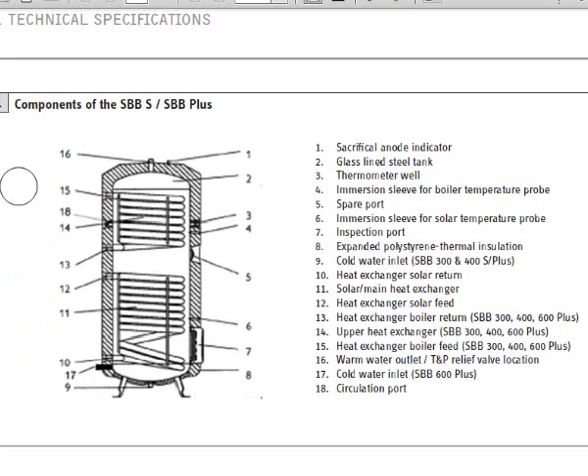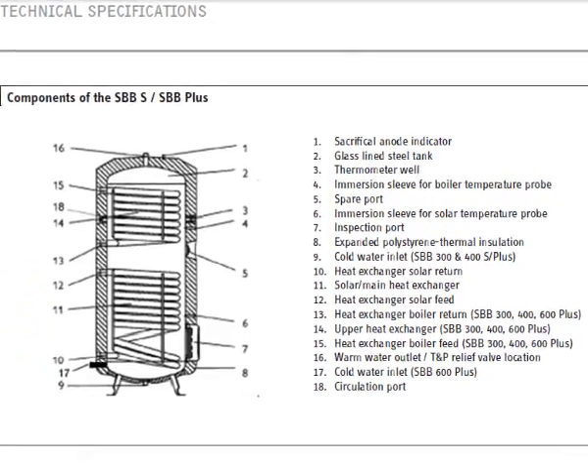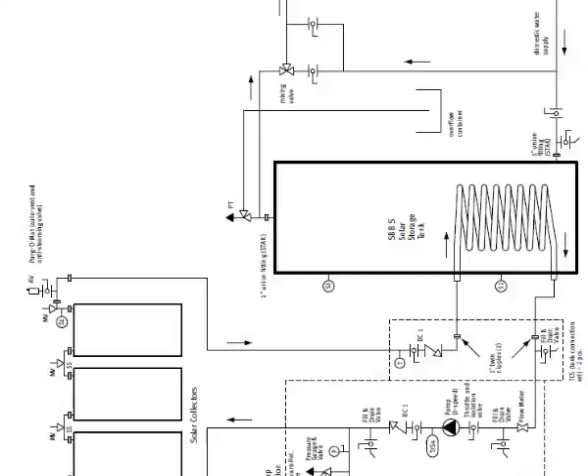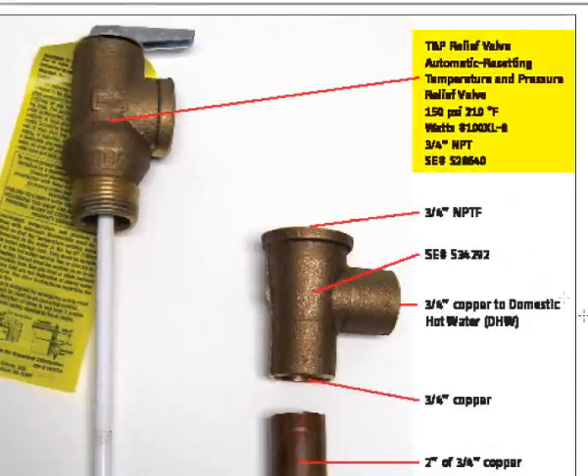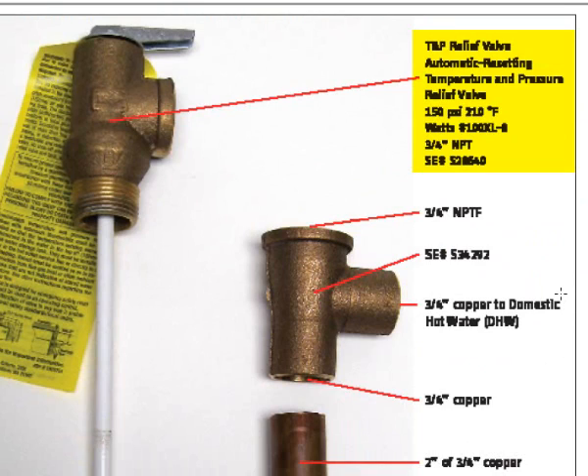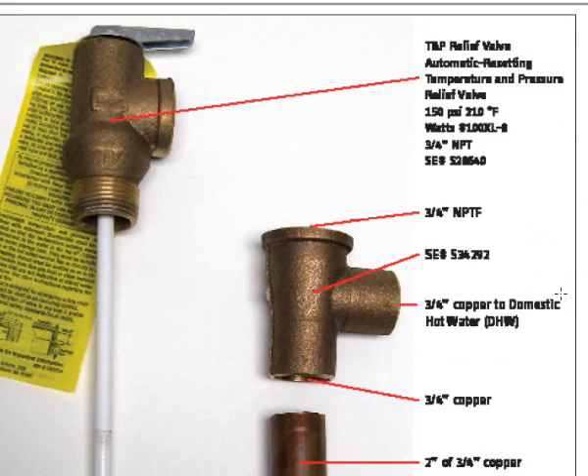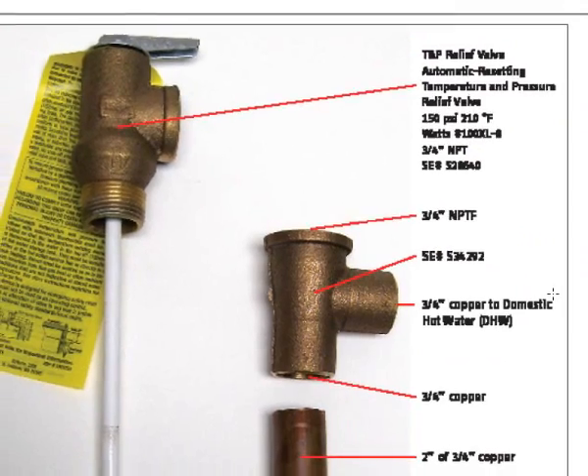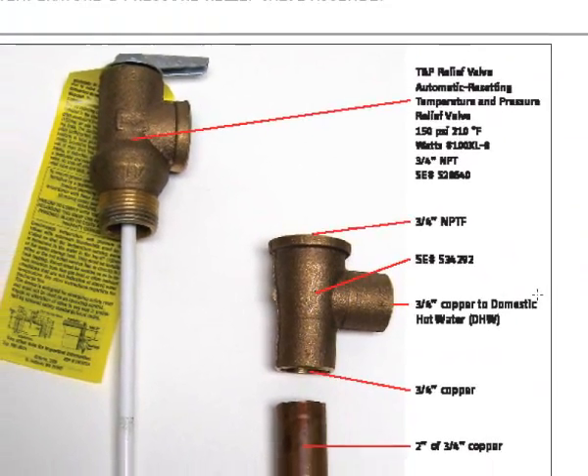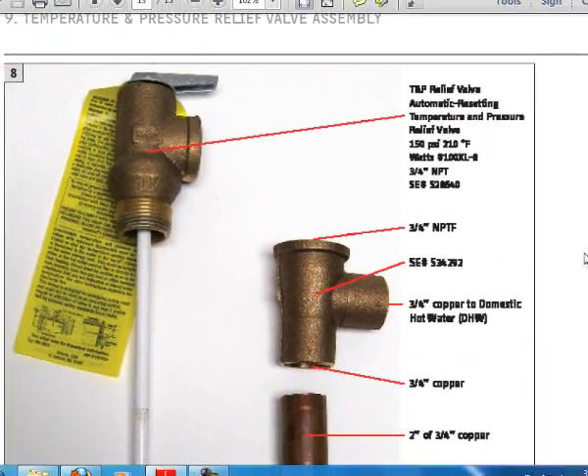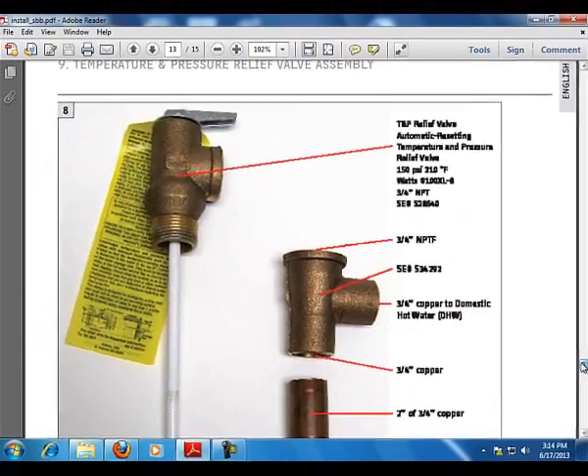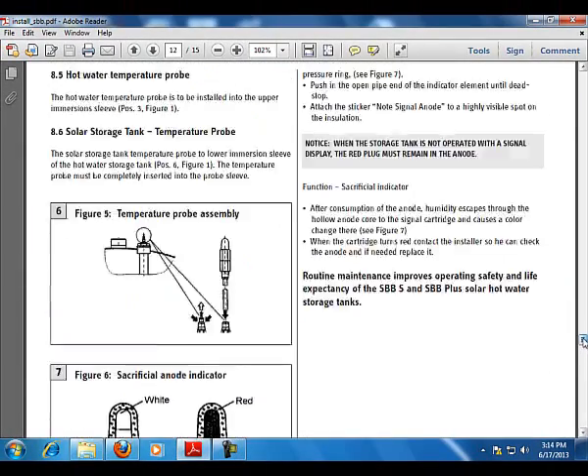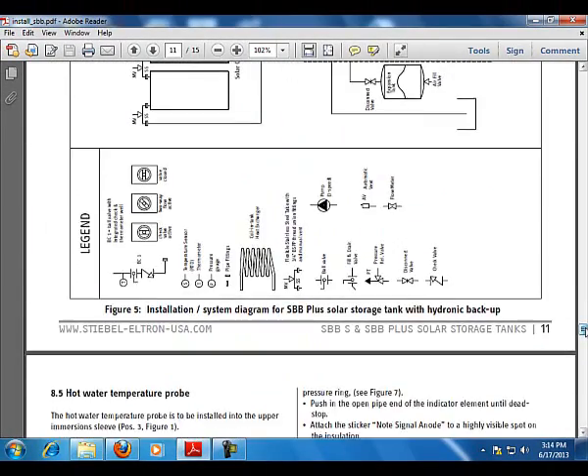Being a pressurized system, we're going to have to have a temperature and pressure gauge in the very top. So if we scroll all the way down to the bottom of this manual, you'll see just a typical pressure and temperature relief valve. It's a standard pressure, single-stage, spring-loaded system, and it's got an operating temperature of 210 with 150 PSI. Most municipal water supplies will provide you with 50 PSI of working pressure where that fluid can flow through.